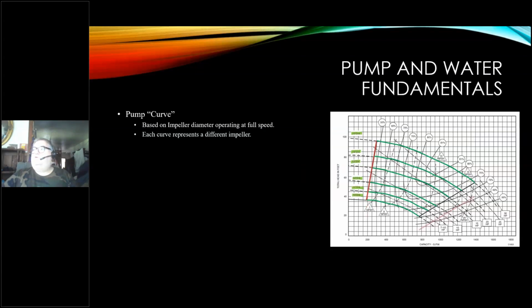Now this curve also includes limit lines. Not all of them do, but those red lines represent where they do not recommend you operate outside of these parameters. Those dotted lines on the curves tell you that this probably is not the best operation for the pump, for whatever reason. It includes both very low flow, below 200 GPM on the bottom left-hand side, and above what we call wide open flow, which is if you had it pumping just into space with nothing resisting flow on the right-hand side. This pump could theoretically pump 1400 GPM with the largest impeller at the very extreme end, but above that they don't recommend you operate in that range. Not all the curves have this, but this one happens to include it, and we'll talk more about that later.